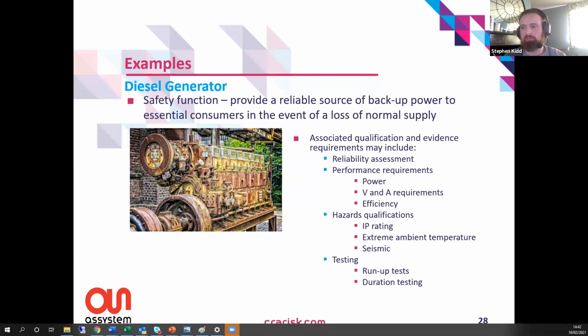So from a hazard qualification perspective, there may be things like IP ratings, so ingress protection. If we've got fire systems in there, we might be worried about deluge. So we might want the systems to be capable of withstanding water dripping on top of them. Extreme ambient temperature I've already mentioned, and seismic qualification. I mean, there's no point in having a backup electrical supply if a seismic event can cause it to fail, because that's one of the main initiators for loss of grid.